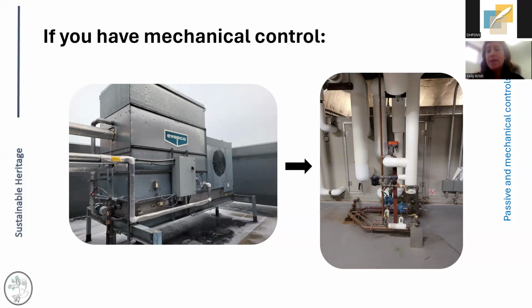I'm going to take just a step back to talk about these photos a little bit. In general, the mechanical control that I'm talking about today involves a cooling coil, which is within an air handler. This cooling coil has chilled water supplied to it that runs through it, and the air is going to pass over it. As a result of the air passing over a cold surface, it's going to drop in temperature as well. And so that cooling coil is what condenses that water out. We're making that bucket small and we're getting the moisture out.